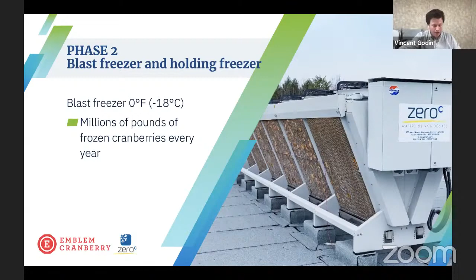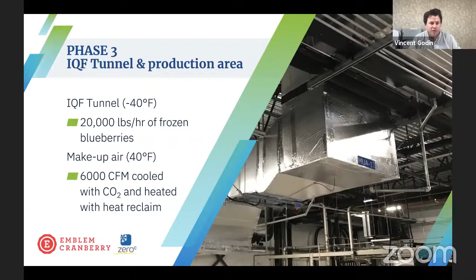The phase 3 that was this year included an IQF tunnel with a suction temperature of -40 F, and that could freeze up, well, it's written 20,000, but we reached 25,000 pounds of wild blueberry per hour this year. It included also a makeup air to change the air in the production room with 6,000 CFM that was cooled with CO2. And on the blueberry production, it included also a hydro cooling of the blueberries before they enter the IQF tunnel with CO2. Actually, that's the photo that you see there with CO2 running in these pipes that was cooling the water.